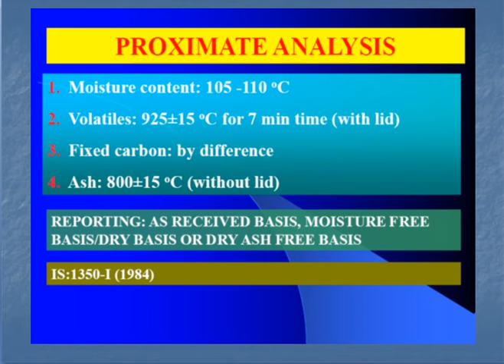So lesser the moisture content, better is the quality of the coal. Why? Because when moisture is present in the coal, and this coal is being heated in the furnace or burnt in the furnace, what will happen? Water has a very high latent heat of vaporization. This moisture will absorb heat, convert to steam, and this will move out with the flue gases.